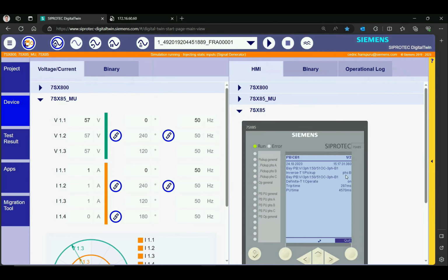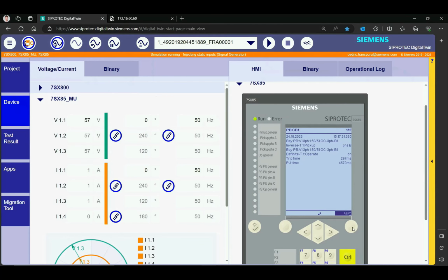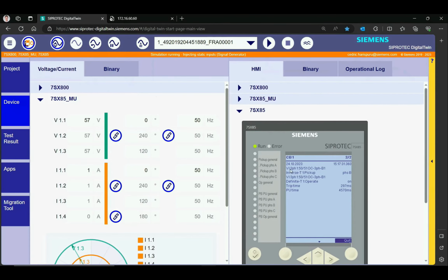It is correct. We've seen the ComTrade file was having a fault on phase B. And you see at the top of the screen, two faults have been created. One with the name bay process bus. This is a protection function that was protecting the second bay with process bus. If I quit that alarm, remains the second fault that was cleared by the other protection algorithm protecting the conventional bay.